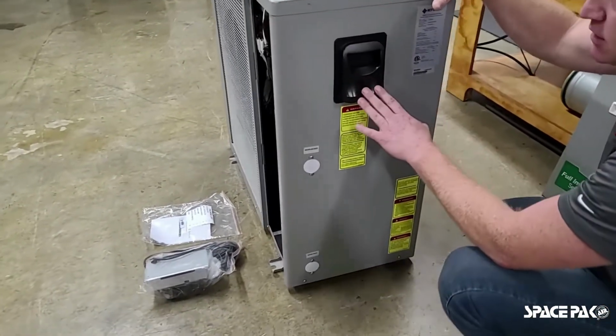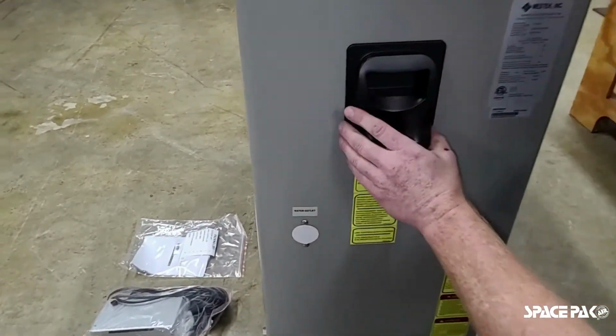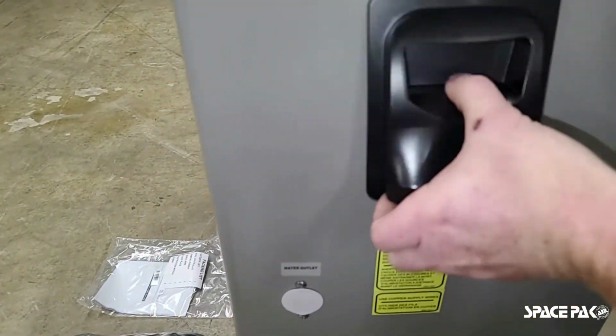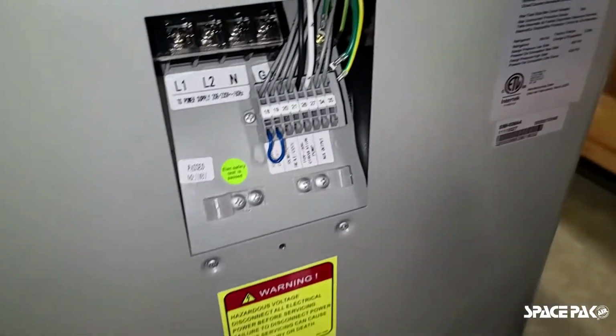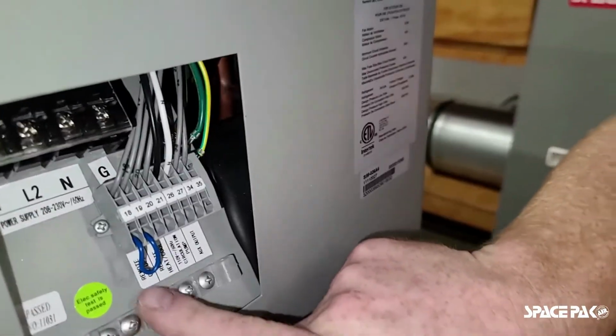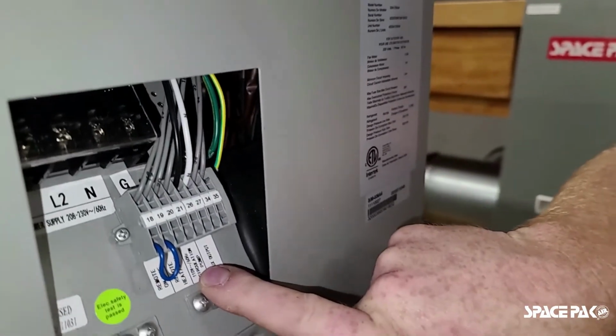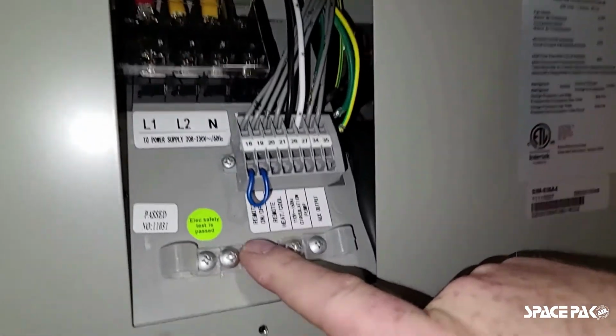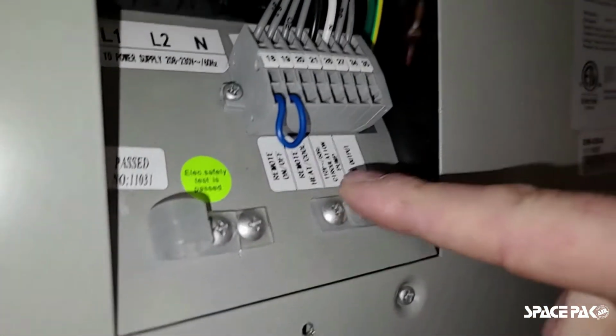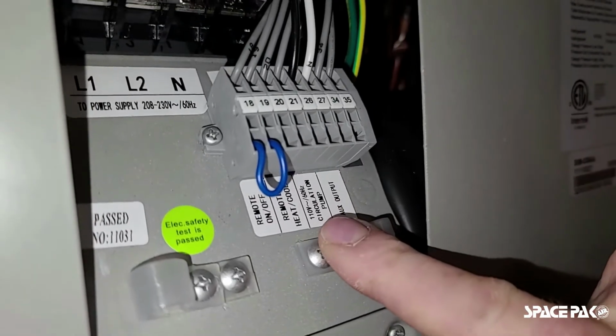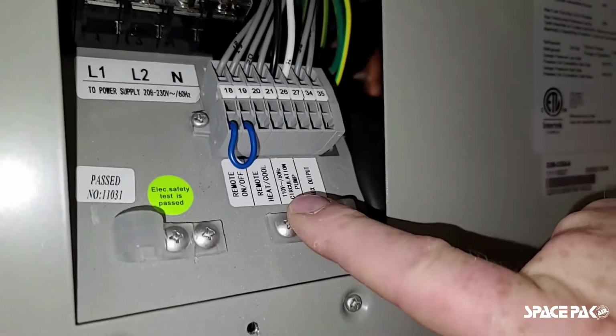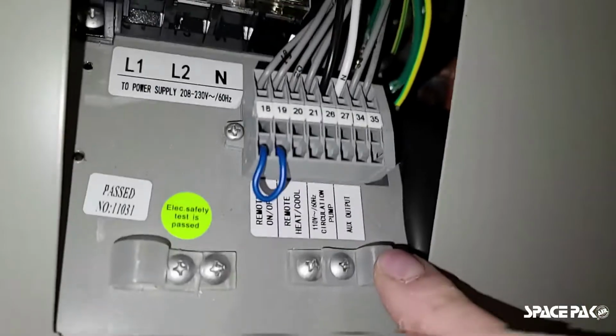While we're on this side of the unit, this is where all of our electrical connections that we need to access are. Cover will come off. Very nice and easy to access. We have our low voltage control. We have our remote on off, remote heat cool. This is where we're going to tie in our circulator pump. Our circulation pump will be tied right in here, as well as our auxiliary output.